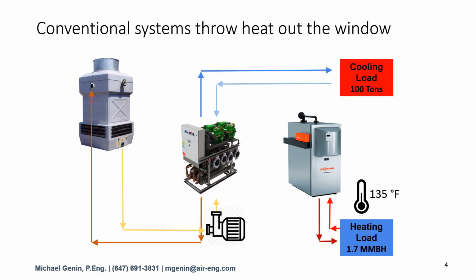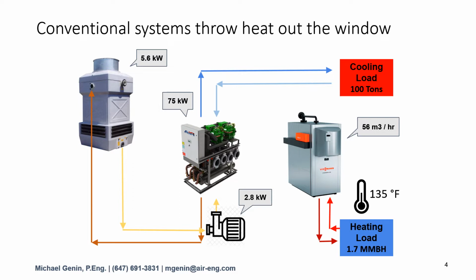Looking at a conventional HVAC system, we literally throw heat out the window. In this case, the window is the cooling tower. The gas boiler maintains the heat load, an electric chiller provides the cooling load, and the chiller is rejecting heat outdoors with this cooling tower. The gas boiler is consuming 56 cubic meters per hour of gas in this example. The electrical chiller has an input, and so do several miscellaneous devices such as the cooling tower fan motor and the condenser water pump. When added up, this system consumes about 83 kilowatts of power.